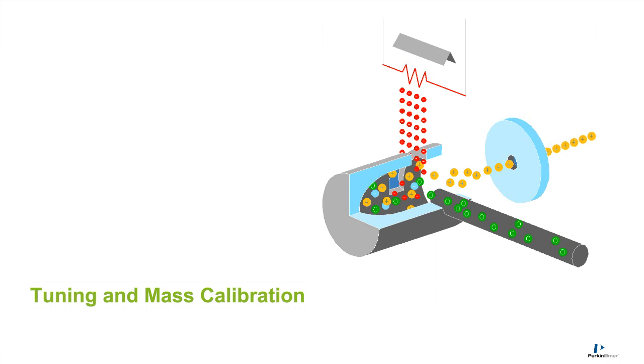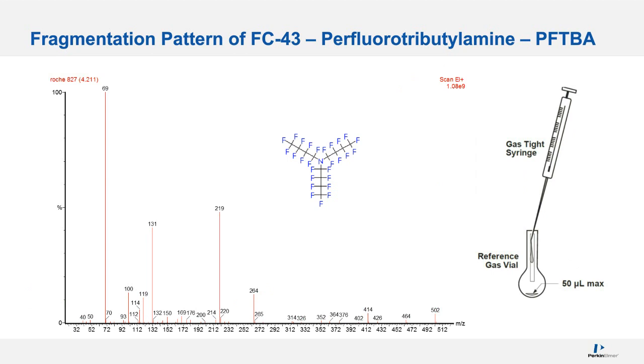Okay, tuning and calibration is the last section. I like to know what the cal gas is, because you may want to pick other fragments. If you have a compound that doesn't have any volatiles in it, you may not care about 69 and 131. So this shows you what the fragments are in the tuning material.